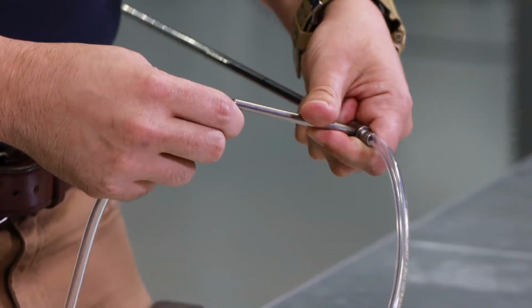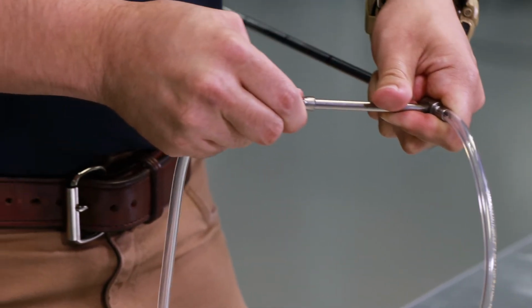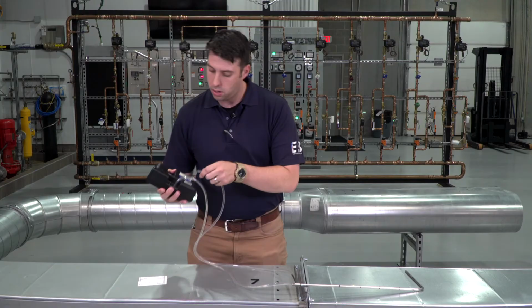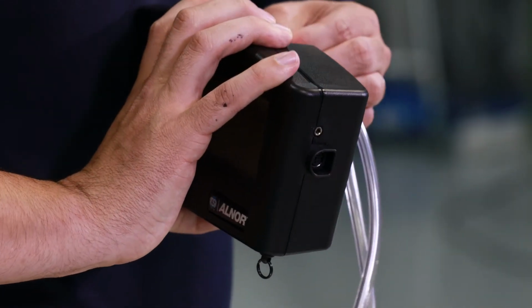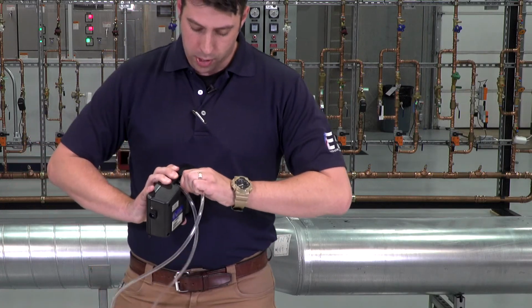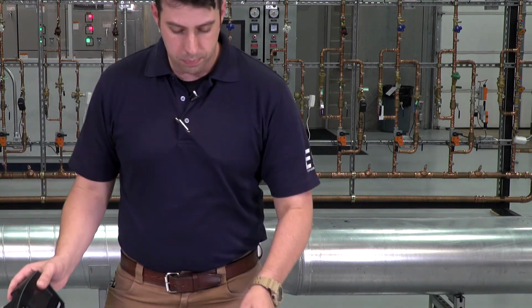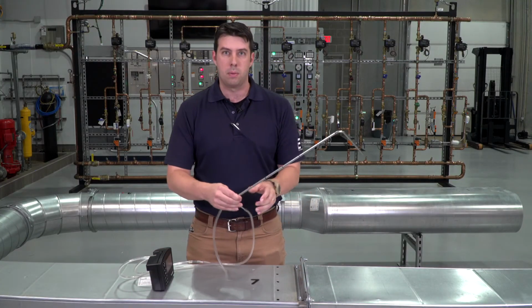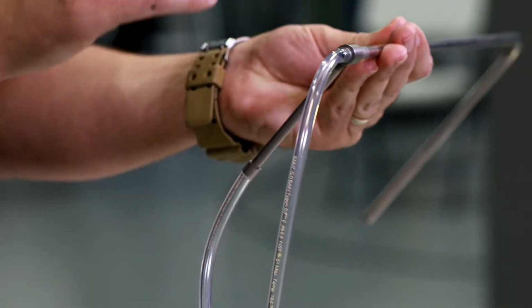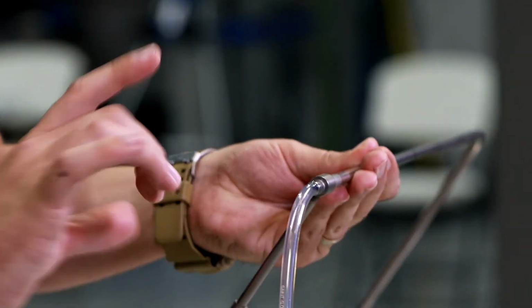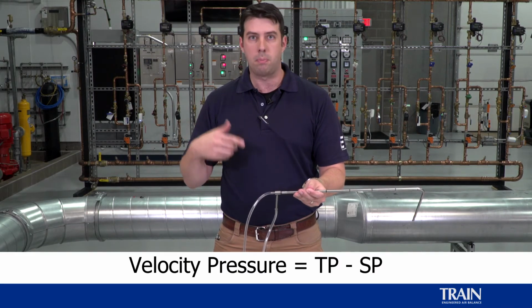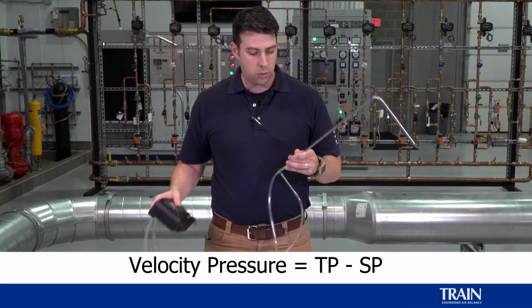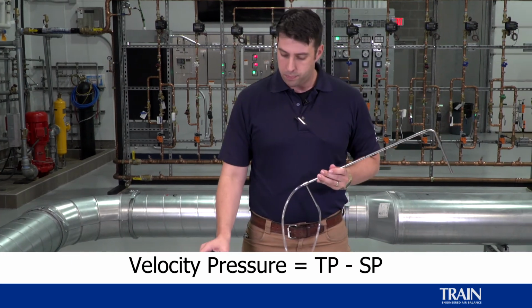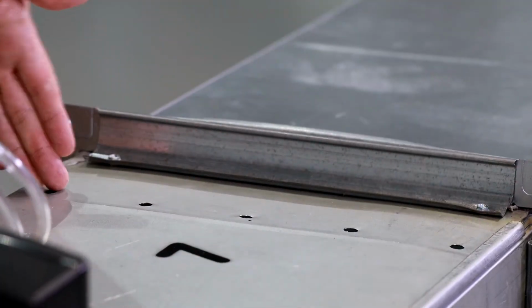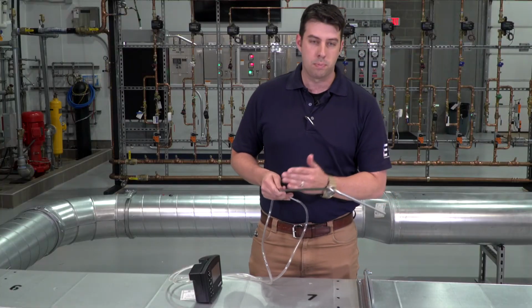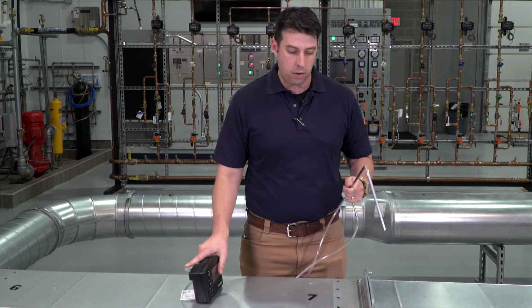Next, we'll take this hose and connect it to the static pressure port of our pitot tube and ensure that it goes onto the low port of the manometer. I want to stress here that the manometer is essentially taking a differential pressure between the total and the static. The velocity pressure is the result of that differential pressure, and the velocity pressure is the total pressure minus the static pressure. So our next step, now that we have everything connected, is to utilize the previously drilled holes and our markings on our pitot tube to actually begin taking our readings in the grid pattern that we've established.